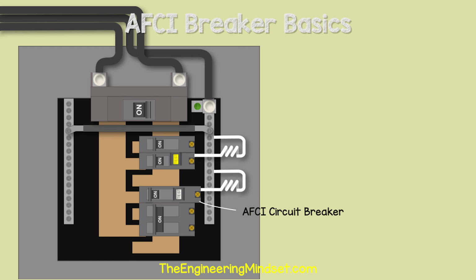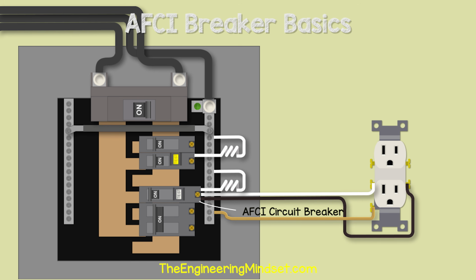AFCIs work by being connected to both the hot and neutral wires. Inside this circuit breaker is a circuit board which measures the circuit and monitors for patterns which indicate an arc fault is occurring. These are installed pretty much identically to how we saw the GFCI breaker.